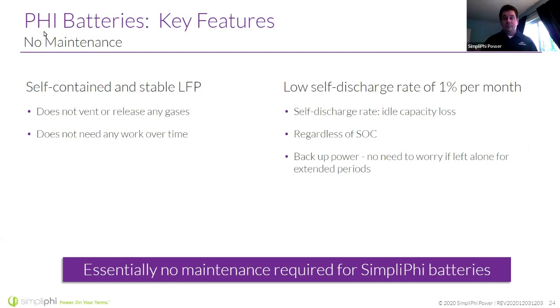Further, our batteries have a low discharge rate. So at about 1% a month, they will self-discharge if they're not connected to anything. So, breaker's in the off position, they're at their warehouse, or maybe the project's on hold for some reason. Storing them is okay. They will ship at about 30% state of charge.